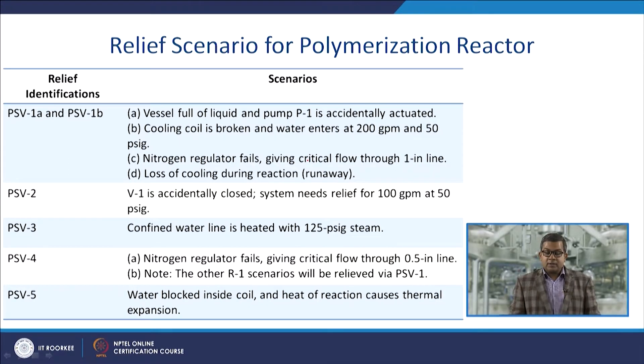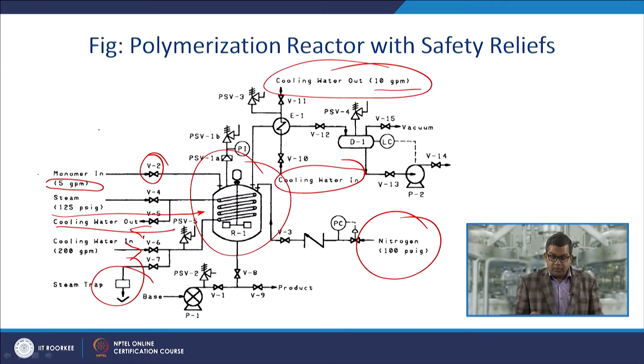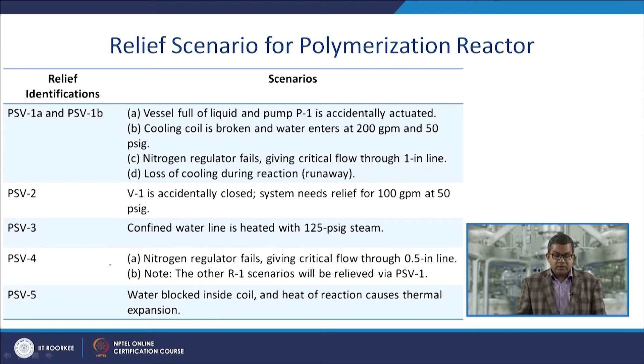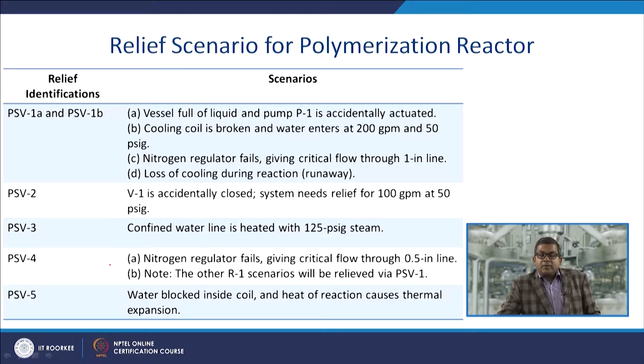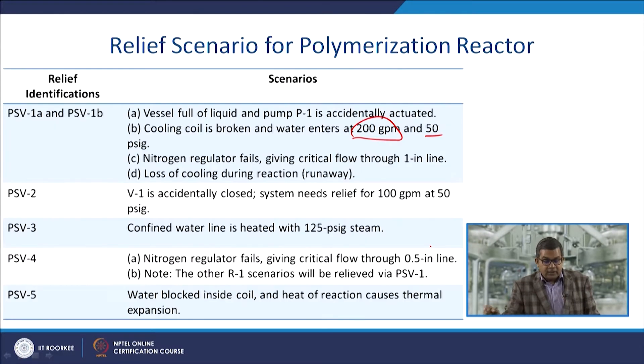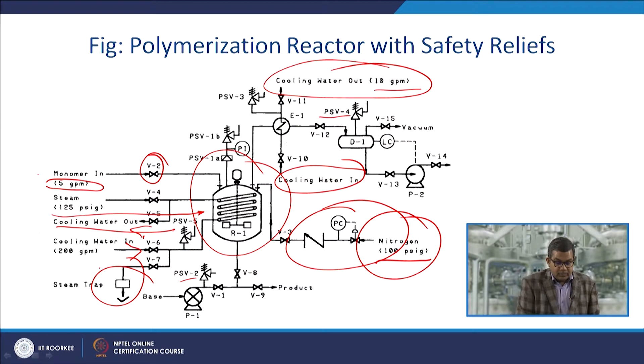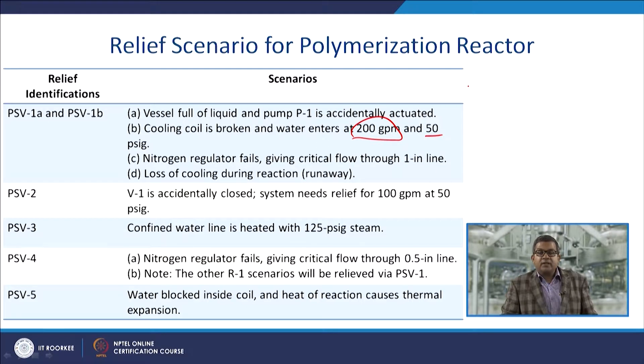The relief scenarios for this polymerization reactor include: PSV-1A and PSV-1B — vessel full of liquid and pump P1 accidentally actuated; cooling coil breakage allowing water entry at a specific pressure; nitrogen regulator failure giving critical flow through the 1-inch line; and loss of cooling during the reaction causing a potential runaway reaction.